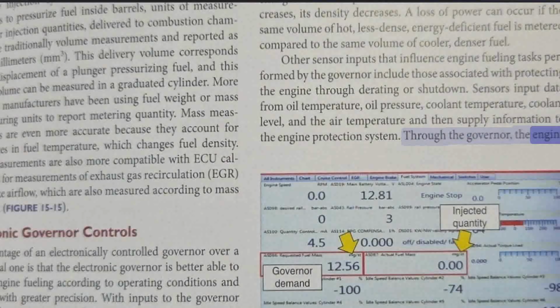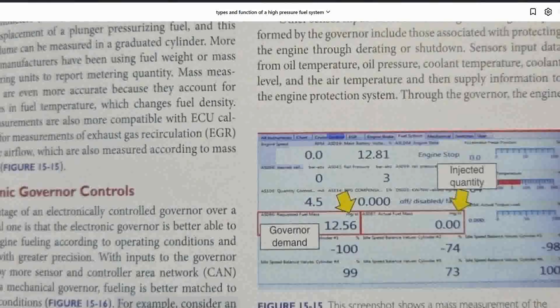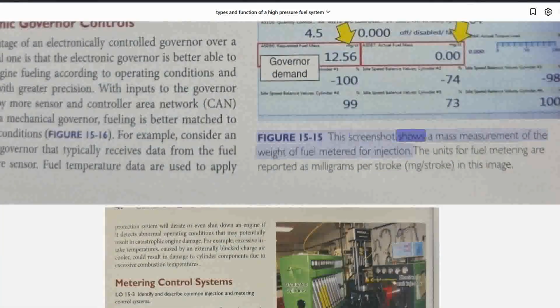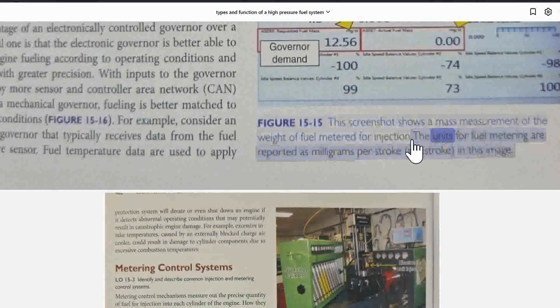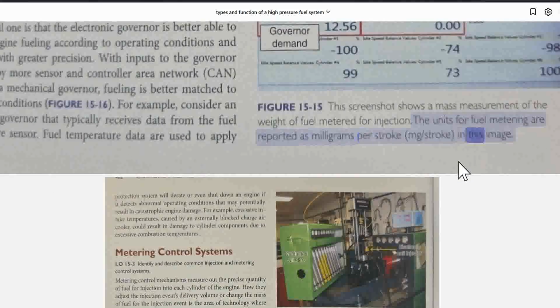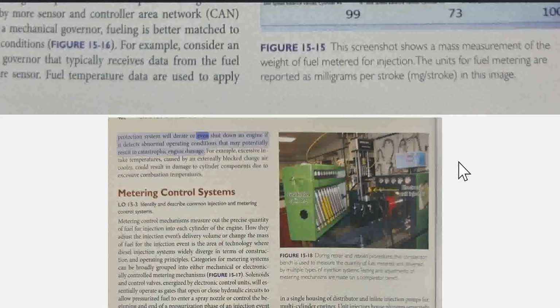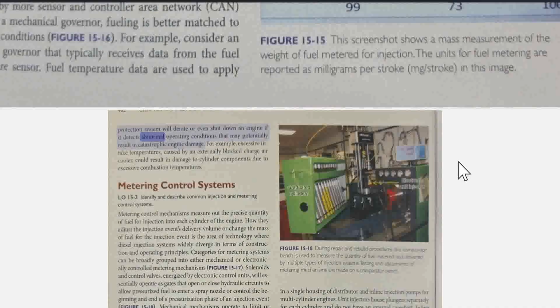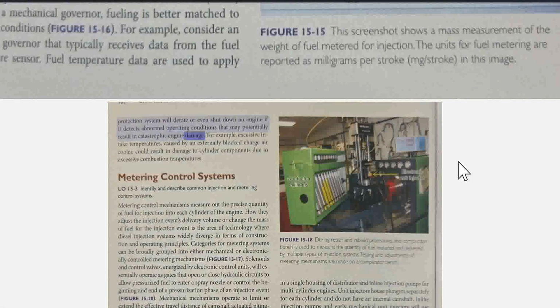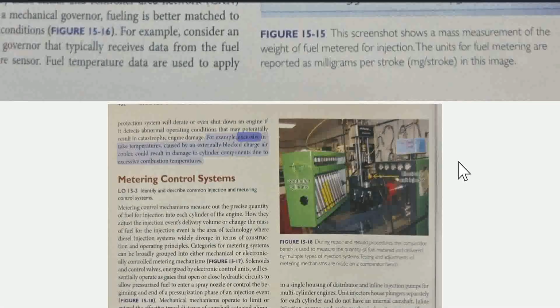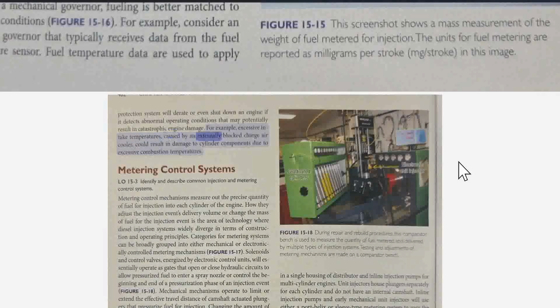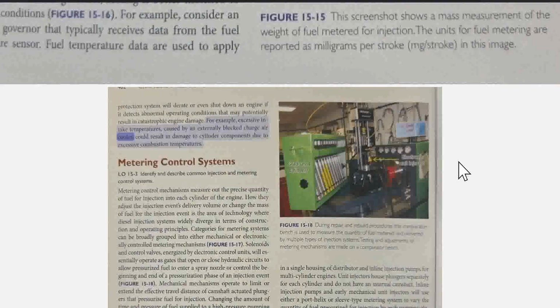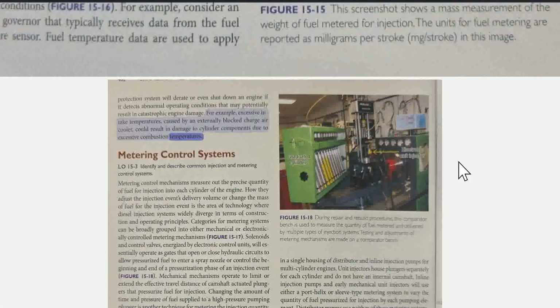Through the governor, the engine will derate or even shut down an engine if it detects abnormal operating conditions that may potentially result in catastrophic engine damage. For example, excessive intake temperatures caused by an externally blocked charge air cooler could result in damage to cylinder components due to excessive combustion temperatures.